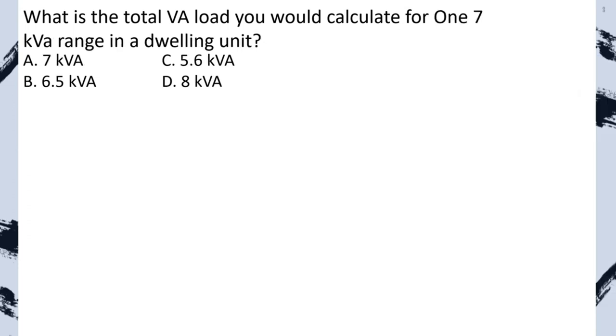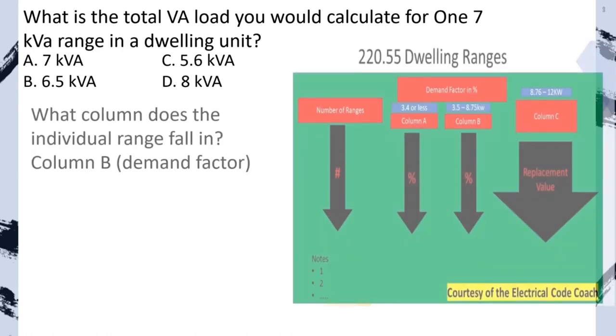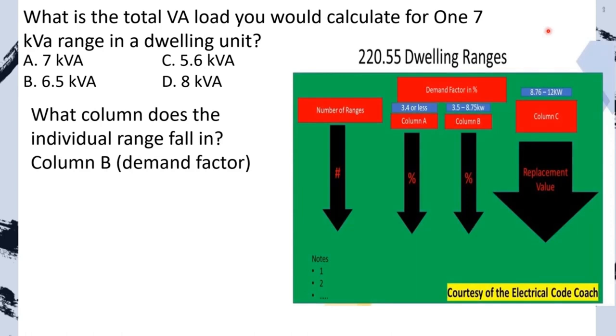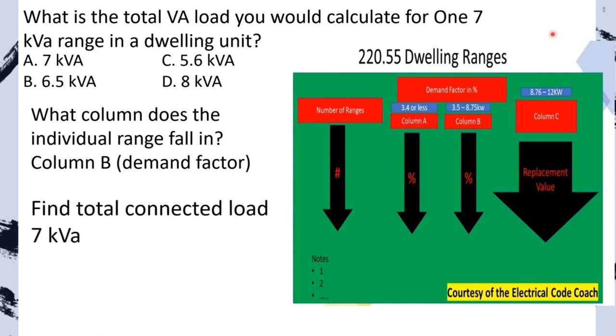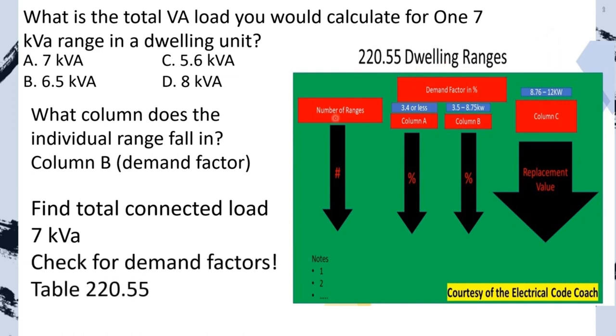Practice problem: What is the total VA load for one 7 KVA range in a dwelling unit? Individual range falls into Column B. Total connected load is just 7 KVA for one range. Check for demand factors: from the table, Column B for one range is 80%. Multiply: 7 KVA multiplied by 0.80 gives our new reduced load. We select C.